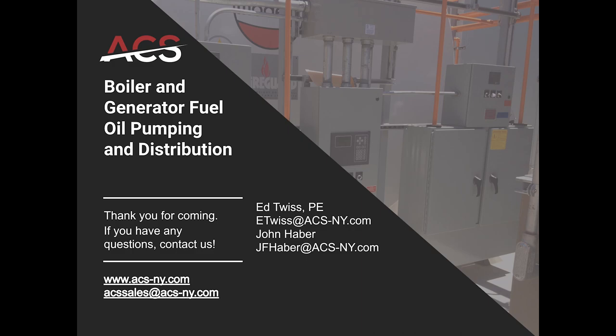So what we recommend is, if you don't turn the oil over in that tank within, we look at it at least a year and a half, 2 years, but there are generator manufacturers who say 6 months. So anything 2,000 gallons or greater, we recommend a filtration unit on there to help keep that oil's longevity.